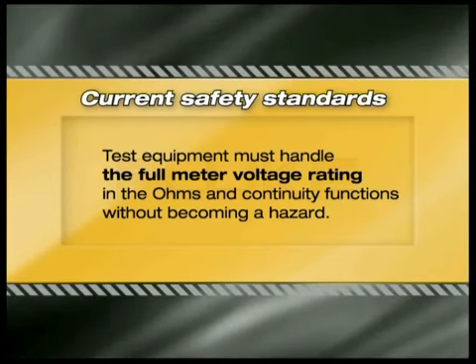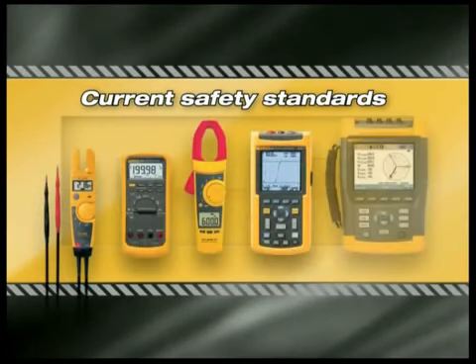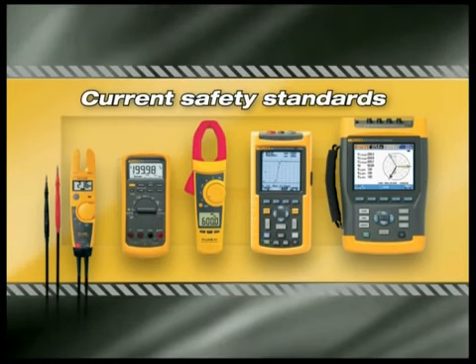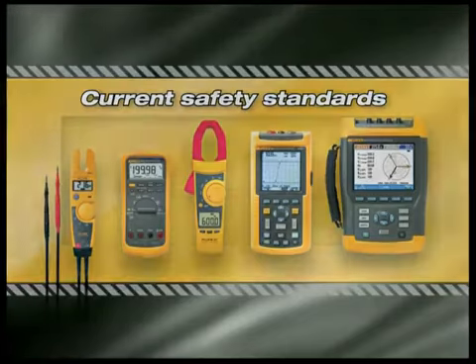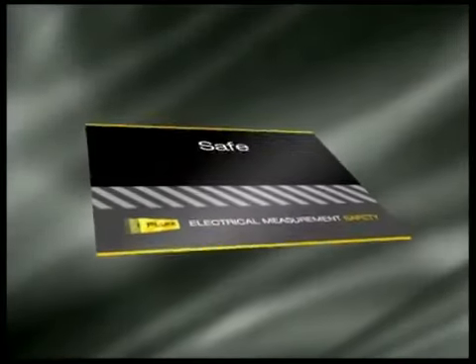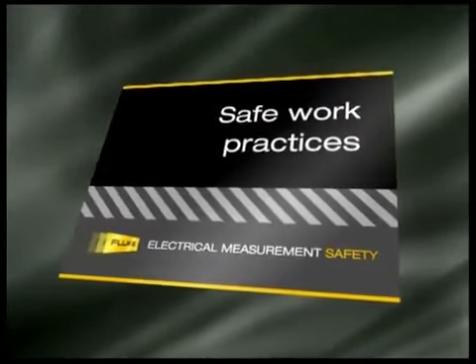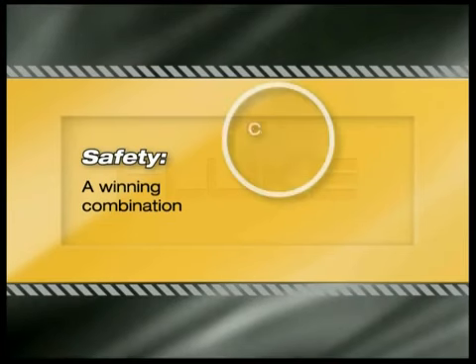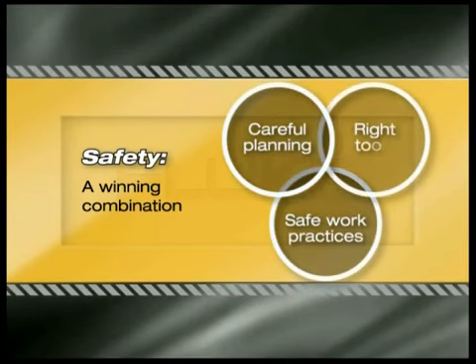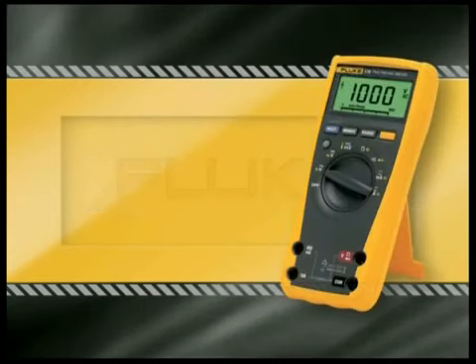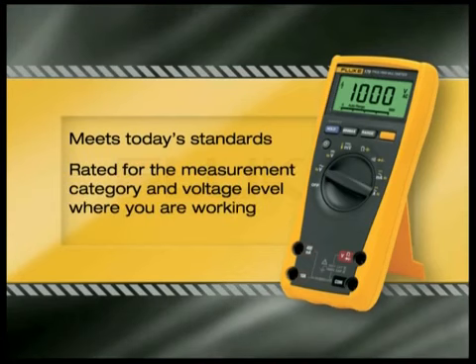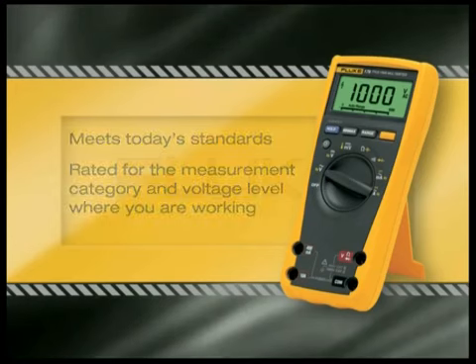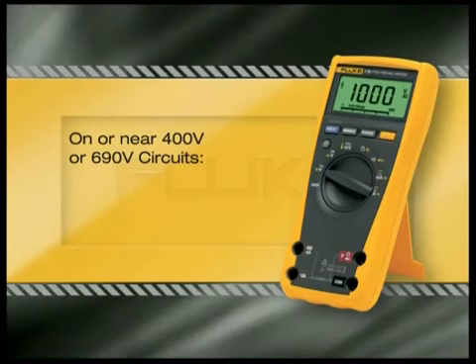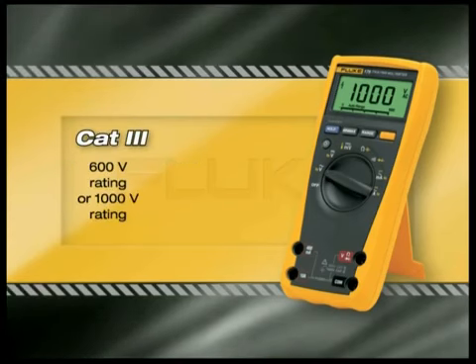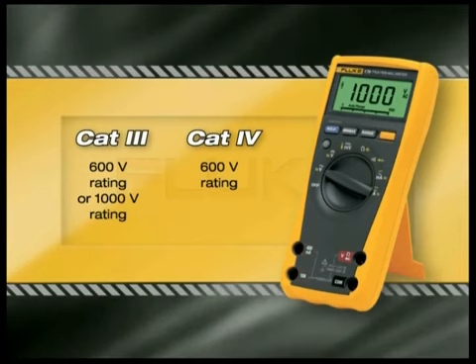To meet the demands of today's high-energy, high-hazard workplace, quality manufacturers have re-engineered their test instruments to make them more reliable and far safer. Safety is the result of a winning combination: careful planning and the correct safe work practices combined with the right tools. Use a meter that both meets today's standards and is rated for the measurement category and voltage level where you are working. If you use test equipment on or near 400 or 690 volt circuits, you should use 600 or 1000 volt Cat 3 or 600 volt Cat 4 meters and testers.